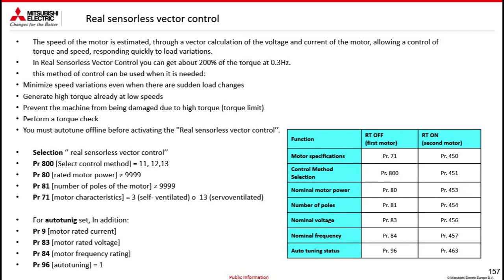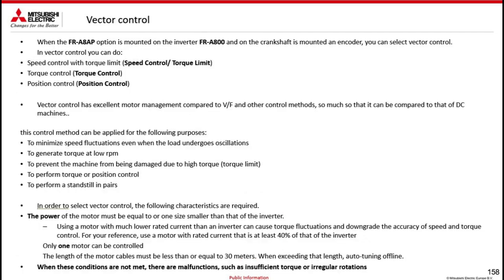So the mode of piloting the motor itself is managed differently, increasing the performance exponentially, which gets us the peak of performance with the vector control, which I remember to be a closed loop control. In fact, up here we talk about the FR-A8AP option. It is the encoder option, so it is an expansion where I can read the encoder mounted on the FR-A800 and also on the FR-E800. I remember the encoder must be mounted on the motor shaft, not after a reduction. Through the vector control, I can manage speed controls with torque limit, torque controls, and position control. In fact, the vector control has excellent motor management compared to the classic V/F, and sometimes it is comparable to that of DC machines.